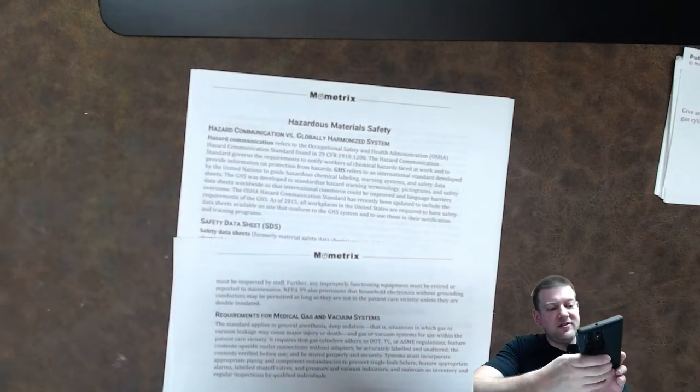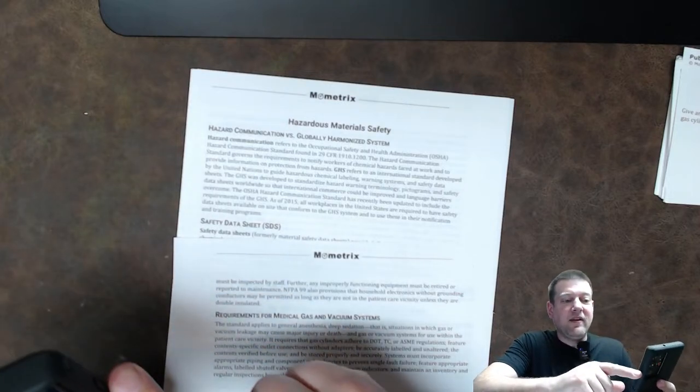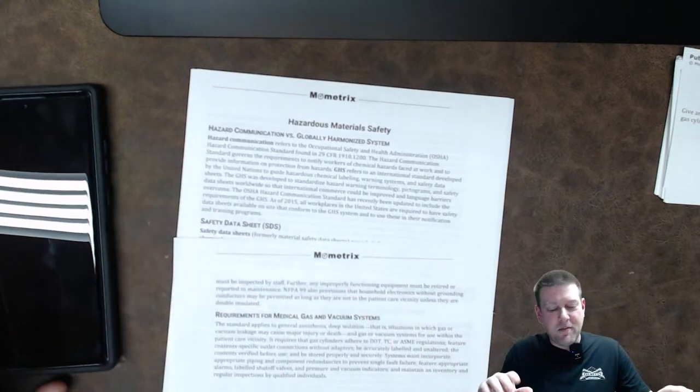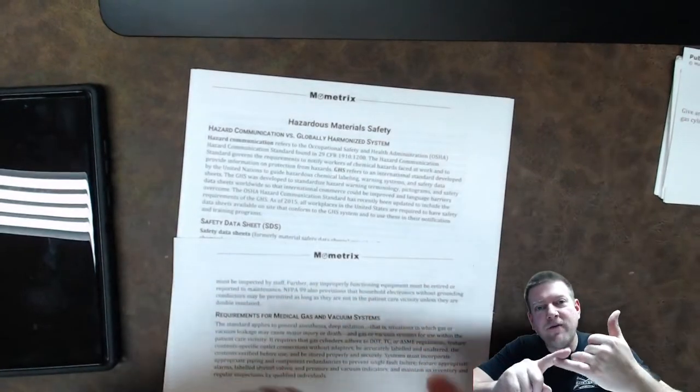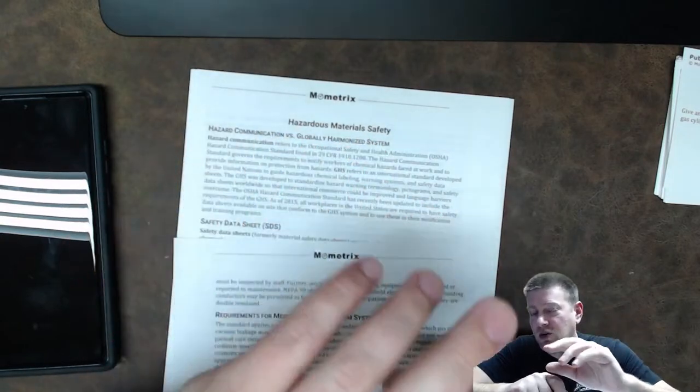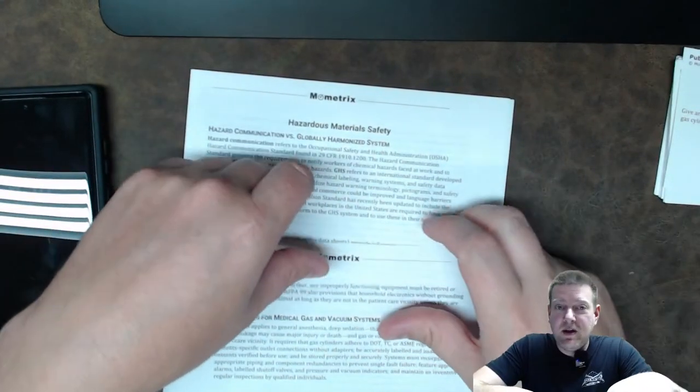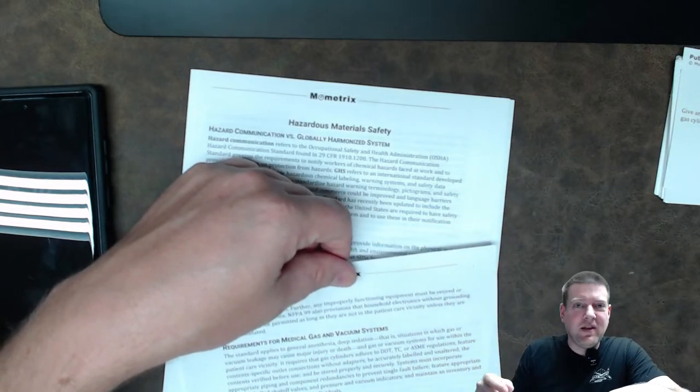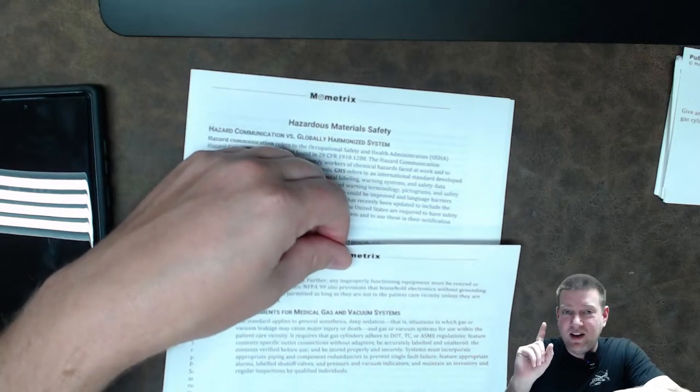That is quite the mouthful, guys, but what does it really say? Sorry, I'm going to shut my alarms off because my phone blows up all the time. So what it says is, everything has to be labeled. You have zone valves, which you're going to find down corridors. Zone valves will shut off the whole entire section. Operating rooms usually have valves local to a specific room because you cannot shut off gases to more than one room, so it's going to be specific. There's got to be, there's usually clear panels where you can see gauges, so it says they have to be labeled appropriately, so each gas has to be labeled, and it has to have a gauge so that you can have a visual indicator of the status of your compressed gases. And down at the bottom, it says you have to maintain an inventory of it, and you have to have regular inspections by qualified individuals.